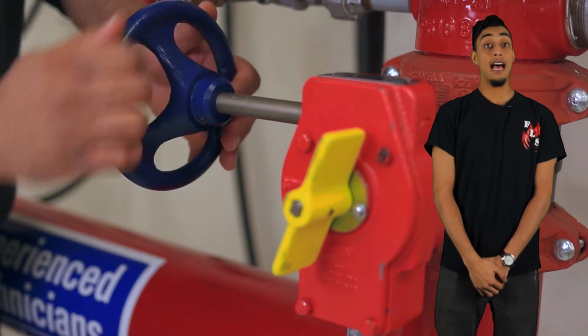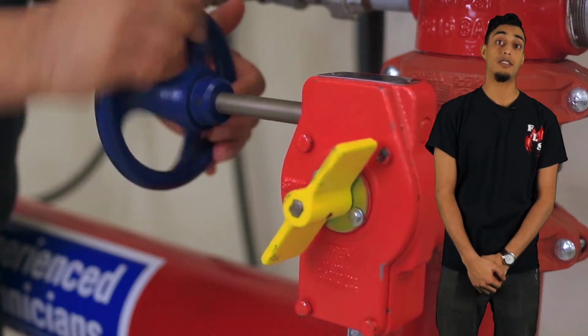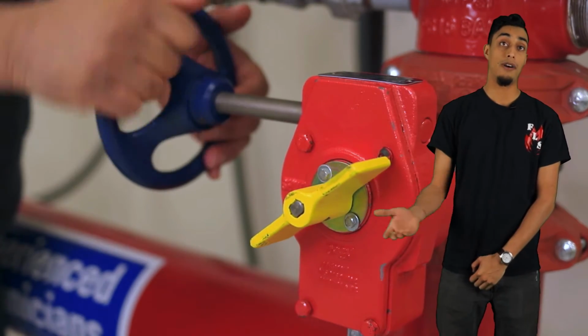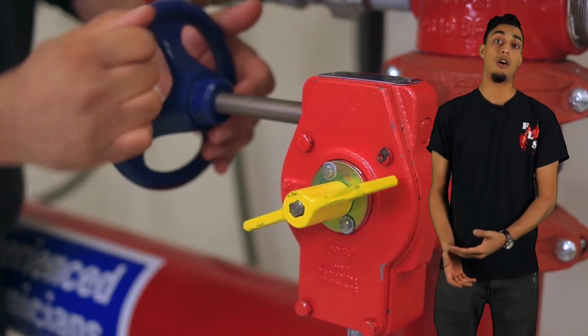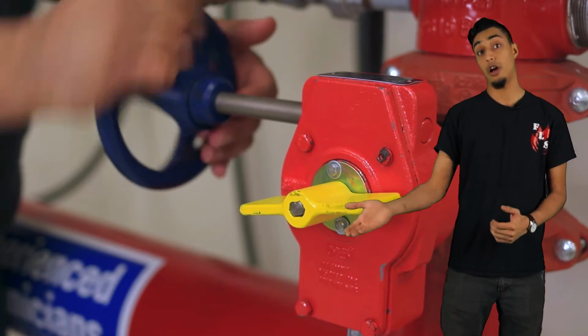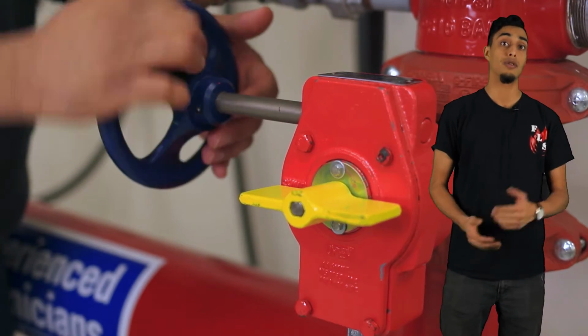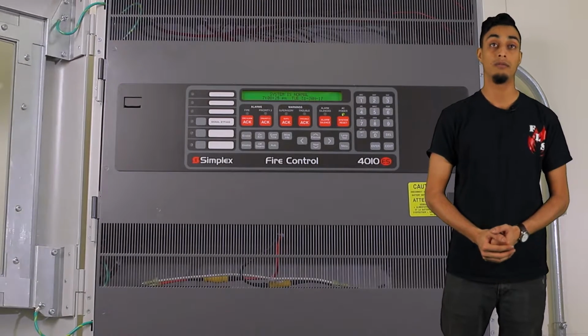Very simply, testing the tamper switch consists of ensuring its function. Therefore, if it was installed with your main control valve, you would shut off your main control valve and ensure that your tamper switch sent a supervisory condition to your alarm panel.